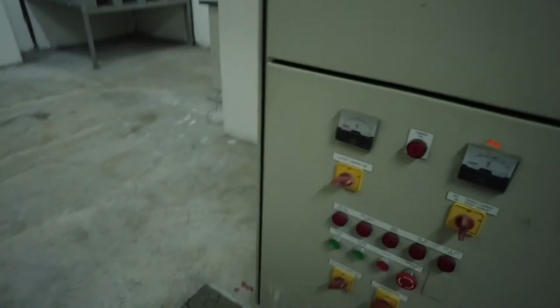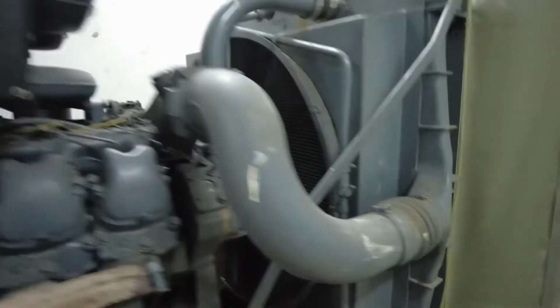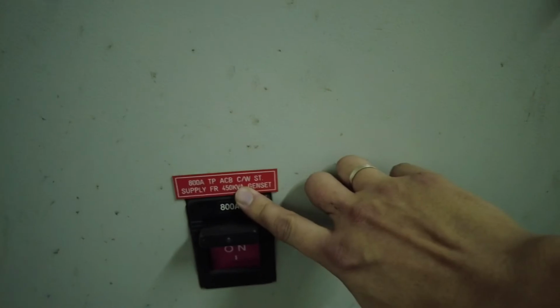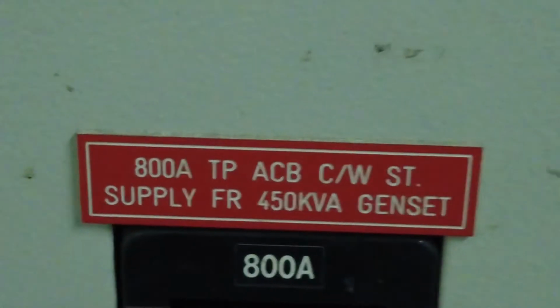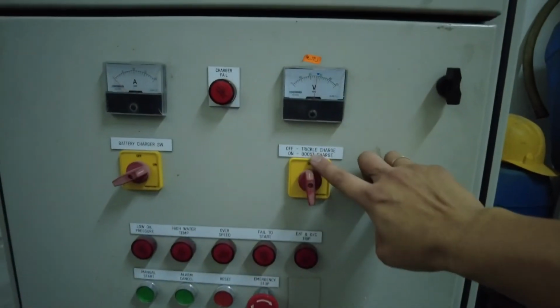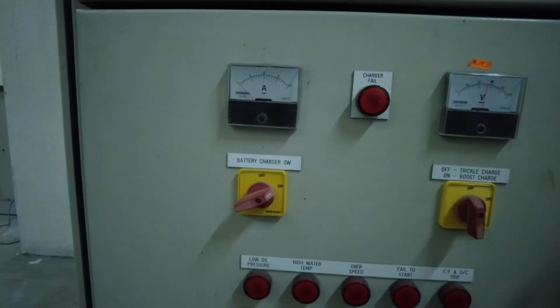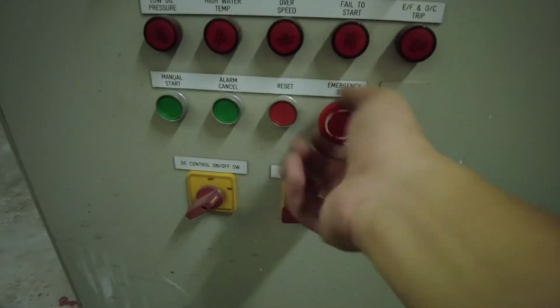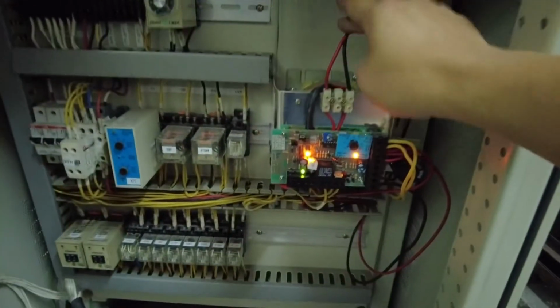How many kVA? Okay, let's check how many kVA. Yeah, here, 450 kVA, 800 amp. First of all, let's check the voltage. Under trickle charge, amp is okay. Under auto mode, emergency stop release, charger is in good condition. Alright, MCCB on.